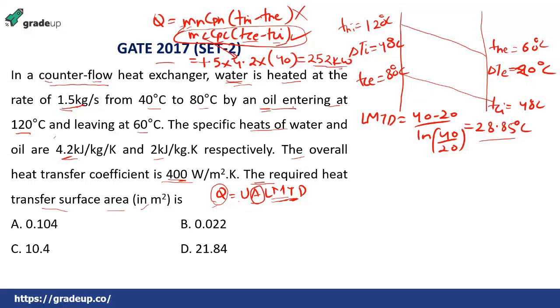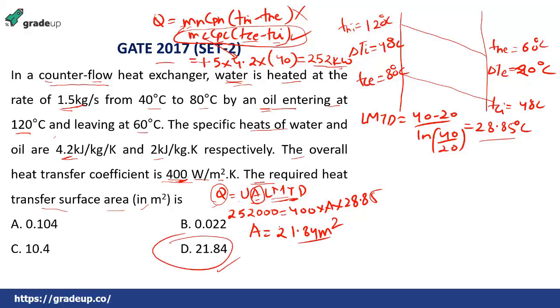Since U is in W/m²·K, convert Q: 252 kW = 252,000 W. Using Q = U × A × LMTD: 252,000 = 400 × A × 28.85. Solving, A = 21.84 m². Option D is the answer.